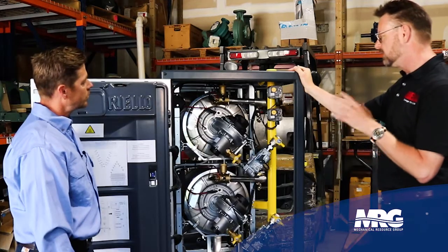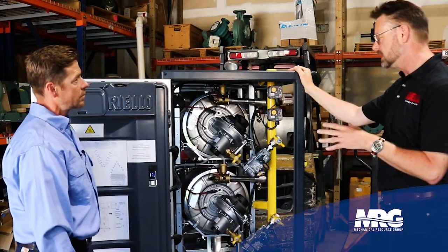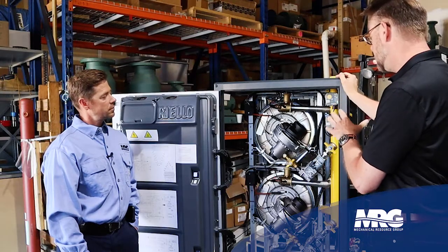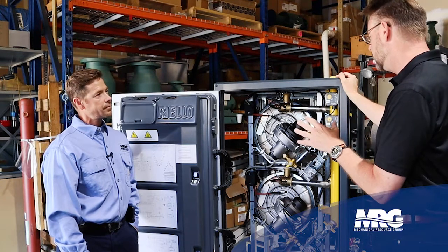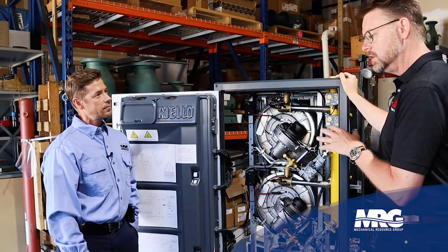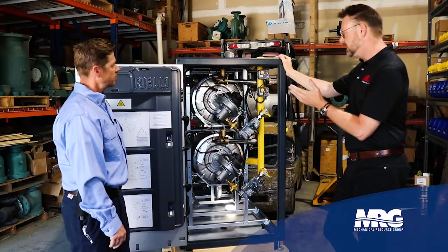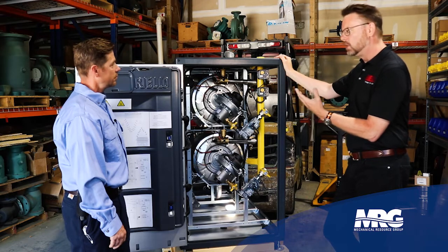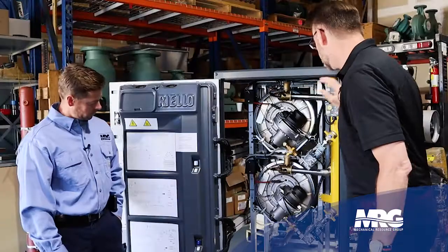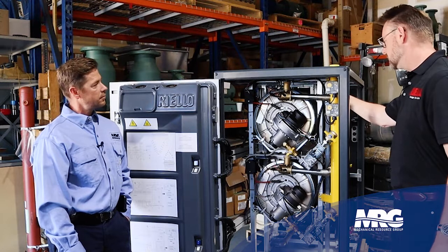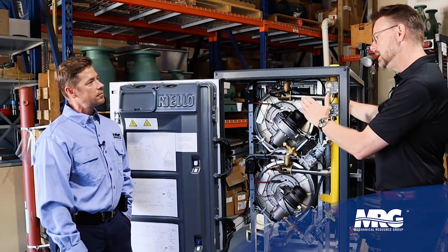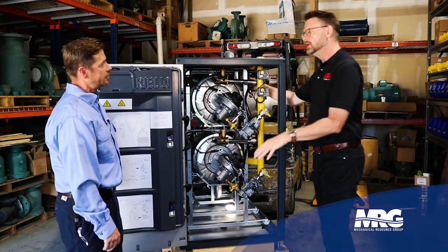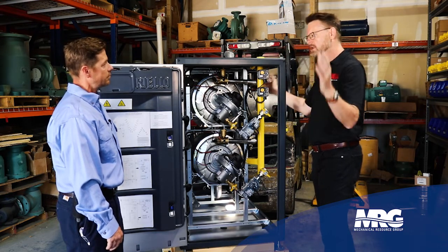Right. Rather than having a flow switch that proves flow on this appliance, what we do instead is we have a flow meter. What the flow meter does is it gives you a readout in gallons per minute, or if you prefer metric, you can do liters per second, and it's going to give you that input. For that thing to have a problem, it would have to clog or otherwise have a bad output. The flow meter exists on each heat engine, and so in that case of a failed flow meter or a flow switch, the whole fired heat exchanger went down. That's right. You had 0 capacity of the unit that was installed.